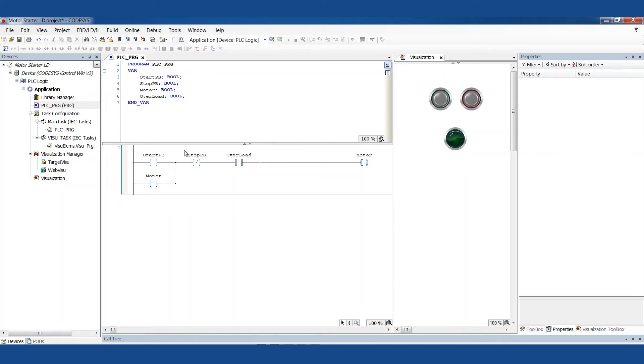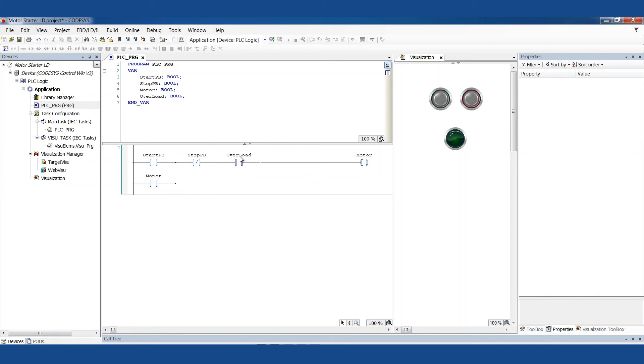When do we want the motor to stop? When the stop push button is pressed. You'll see this is a normally closed contact, which is very common for stop conditions. We've also got an overload — very common for motor starters. If the motor overloads, this is basically a circuit breaker built into the motor starter. There is a contact that stays closed until it overloads, and then we know it's overloaded. When that happens, we stop. We also want the motor to stay on even if we're not pushing the start button, which is where the latching circuit comes in — always in parallel with the start condition. When the motor is on, keep it on until the stop button is pressed or the overload trips.